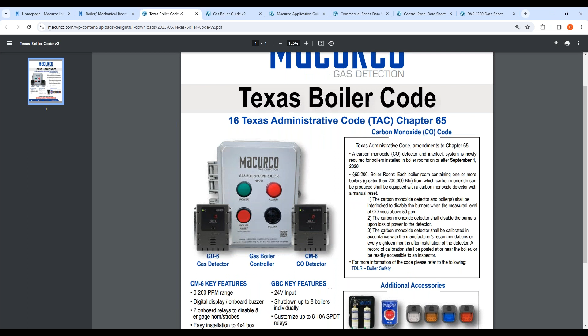the boiler mechanical room, I'll just use Texas as the example right now. Per their state code, which is what, Texas Administrative Code, Chapter 65, they recommend, I think, every 18 months, if I'm not mistaken, where you have to calibrate the detector during that time period. Yeah, it says after every 18 months of installation, the detector needs to be calibrated. So we recommend annual calibration. If your companies are very big on service, it is a very nice way to have that extra added income. But it also keeps the detectors paired up to do what they're supposed to be doing.